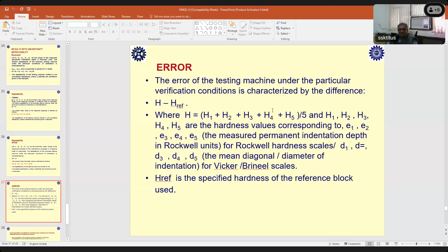Then if you are having a reference block, you can see how much variation is coming from the reference block, which is calibrated using a primary standard machine. That will give you the error in that machine when you are calibrating it in the indirect way, so that you can account for separately. Whenever you are calibrating a machine, after measuring 5 readings, you have to check the resolution of the machine. Then you have to check the standard uncertainty coming from the repeated measurement. Then you combine this with the standard uncertainty given for the reference block. Combining these 3 things, you can give the total overall uncertainty of the machine, and finally you can include the error in the measurement by seeing the difference between the average value and the reference value. So that is how ultimately it is achieved.